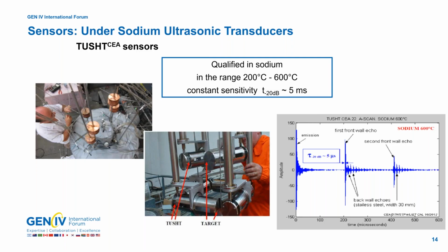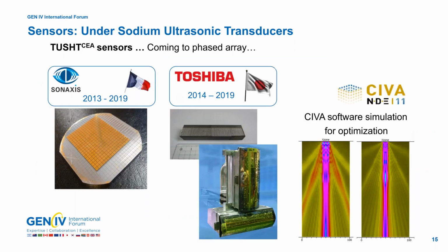I am moving to the next slide. What about other transducers? Of course, the former transducers I showed you was a single element transducer, and it is a piezoelectrical transducer. And in that family, we also developed phased array transducers. So in collaboration with the French company Sonaxis, we developed the transducers that you can see on the left side, which is a transducer with many dozens of elements, each of them being independent from the others.